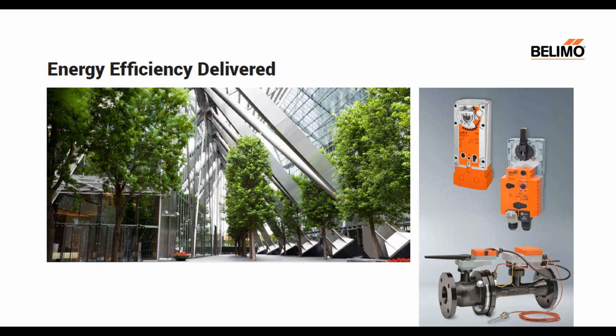The Belimo energy valve provides transparent energy monitoring while maintaining design delta T. Automatic reports show actual and historical performance data and can recommend a new delta T set point for additional energy savings. As an IoT device with cloud-based services, you can benchmark coil performance, analyze glycol concentration, store energy data, produce commissioning reports, and send alerts. And with the energy flow map, you can visualize where the energy is consumed and correct as needed.